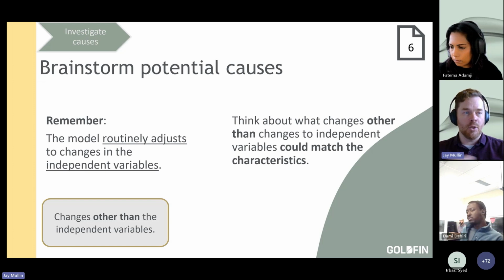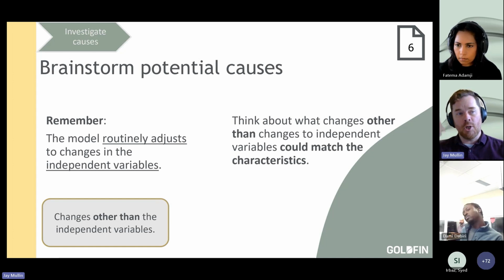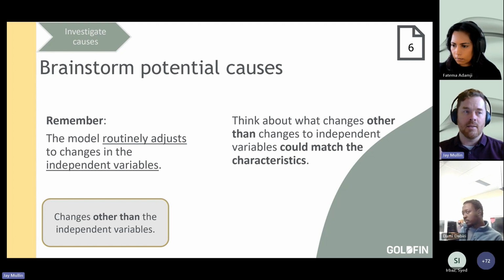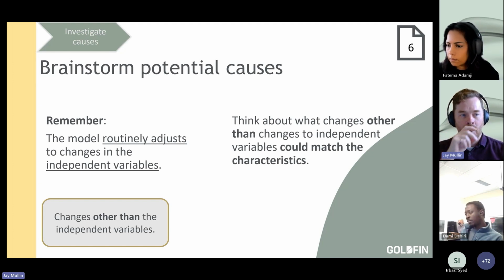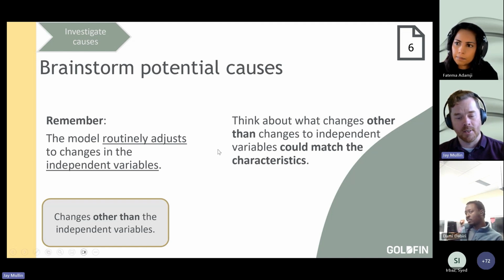A potential explanation there would be the BAS setbacks. The model doesn't see what those BAS settings are. So if we change those to turn more stuff off on the weekend, that's going to start showing up as a change in slope in the model. Those are changes other than the independent variables.